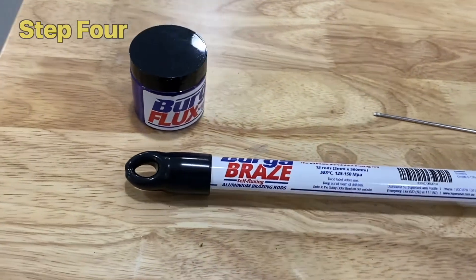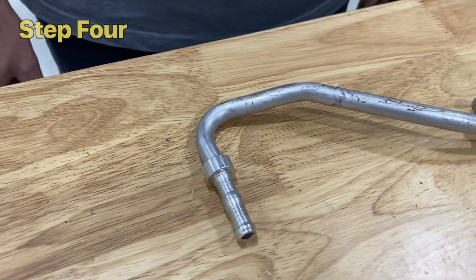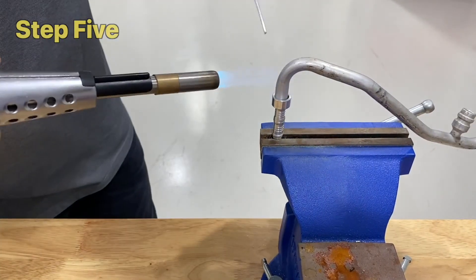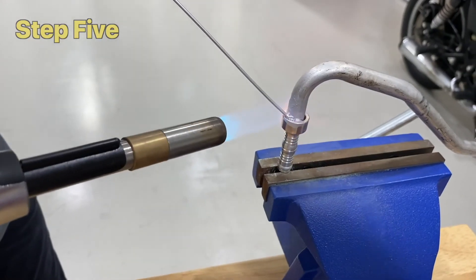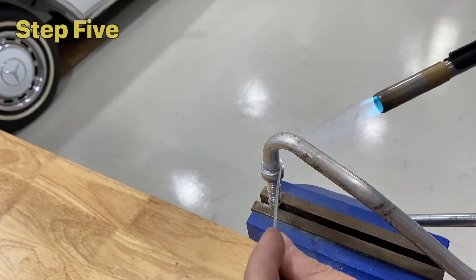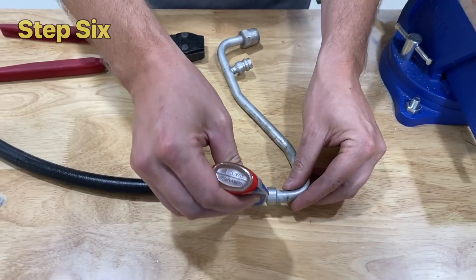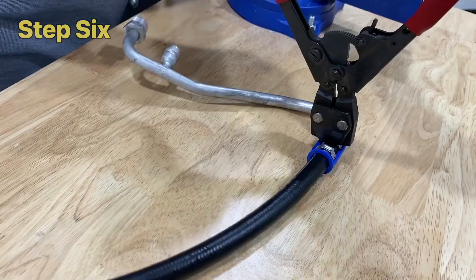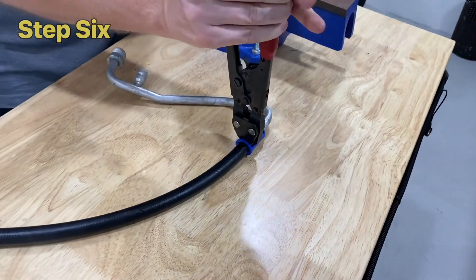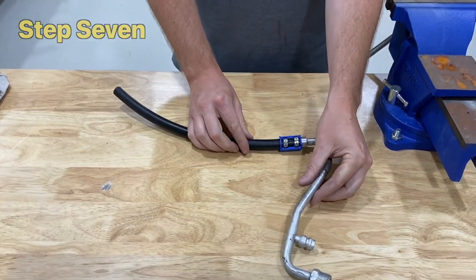Step 4: Place the BurgaClip braze-on tail onto the prepared pipe. Step 5: Braze using Burga Braze and a handheld propane or butane gas torch. Step 6: Secure BurgaFlex 3090 hose to the tail using the industry-leading BurgaClip system. Step 7, if required, is to rotate the fitting to the desired orientation.